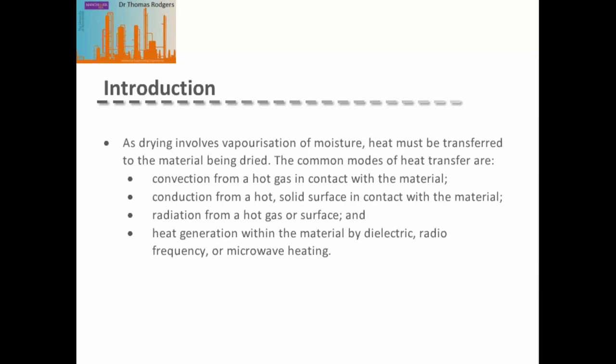As drying involves the vaporization of moisture, heat must be transferred to the material being dried. There are four common modes of heat transfer: convection from a hot gas in contact with the material, conduction from a hot surface in contact with the material, radiation from a hot gas or surface, or heat generated within the material by dielectric, radiofrequency, or microwave heating.